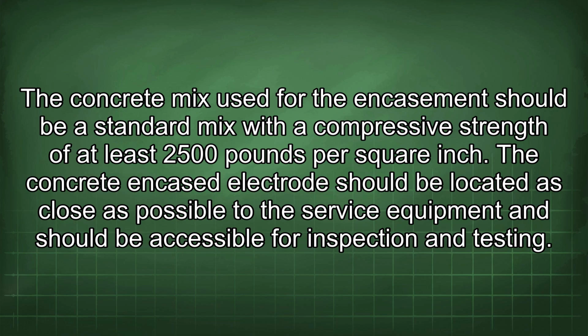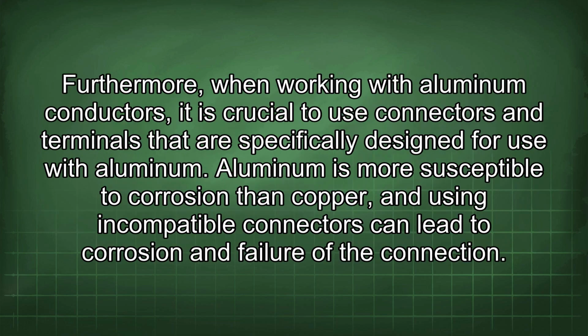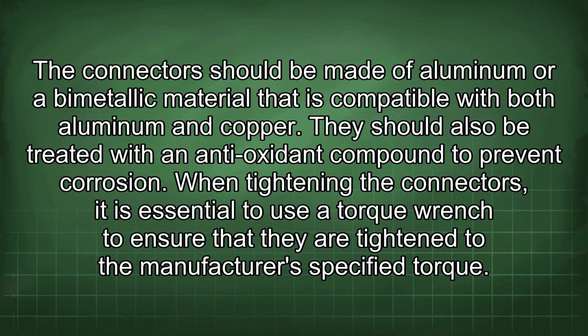The concrete encased electrode should be located as close as possible to the service equipment and should be accessible for inspection and testing. Furthermore, when working with aluminum conductors, it is crucial to use connectors and terminals that are specifically designed for use with aluminum. Aluminum is more susceptible to corrosion than copper, and using incompatible connectors can lead to corrosion and failure of the connection. The connectors should be made of aluminum or a bimetallic material that is compatible with both aluminum and copper. They should also be treated with an antioxidant compound to prevent corrosion.